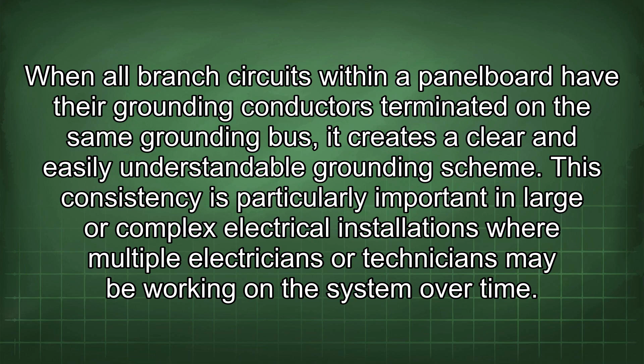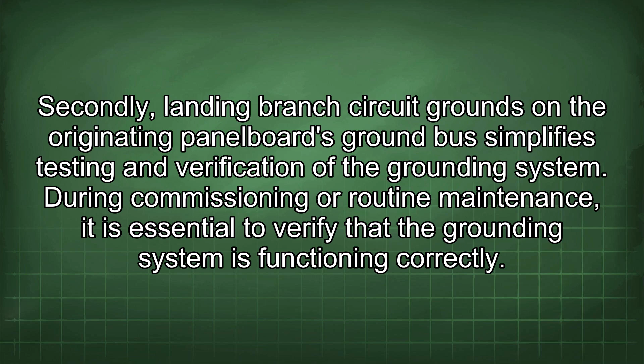Secondly, landing branch circuit grounds on the originating panel board's ground bus simplifies testing and verification of the grounding system. During commissioning or routine maintenance, it is essential to verify that the grounding system is functioning correctly.